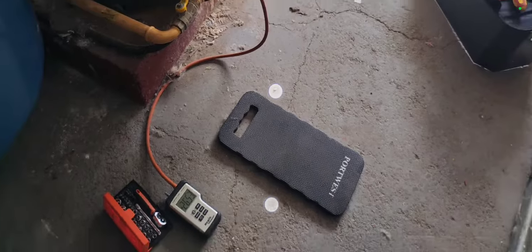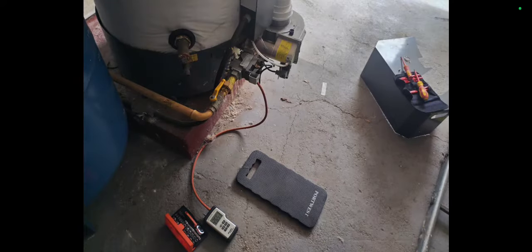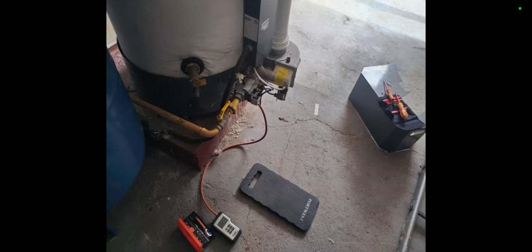Here's another plant room where I went in and the hot water was off for the summer. So the heating was off for the summer. The hot water boiler was not working. It was an Elco boiler, gas-fired water heater, should I say. So I was having a look at it, and here you can see I'm carrying out a check to see if there's actually gas pressure going into it.